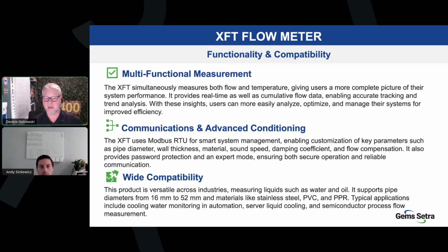Now, not everybody has Modbus, and it's not required to use it, but it is available as an added benefit to talk with your building automation system. Modbus gateways can be used too to convert that to Ethernet or BACnet so that you can support whatever protocol you are using. The Modbus RTU enables customization of the key parameters like pipe diameter, wall thickness, the pipe material, sound speed, damping coefficient, and flow compensation. Now, sound speed and damping coefficient, we'll go into that on our next slide. There's password protection too, because there are advanced calibration menus that you might not want some users to have access to.